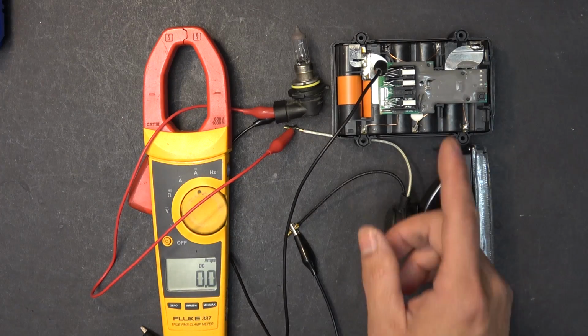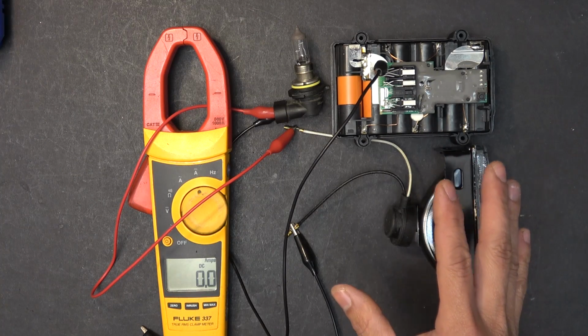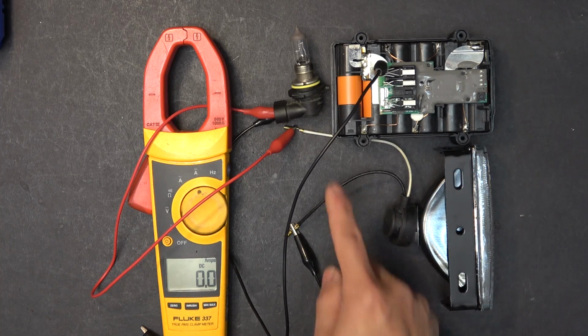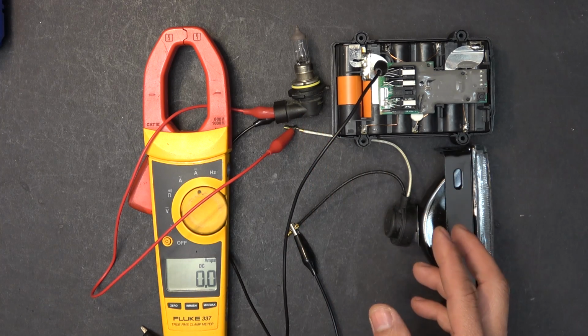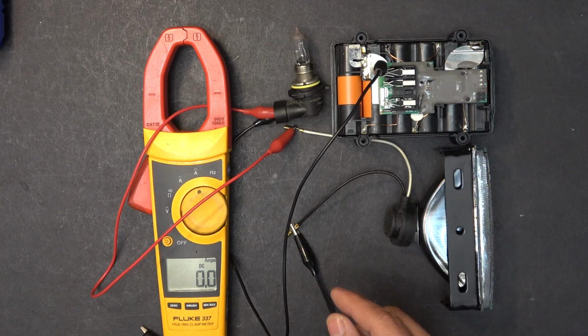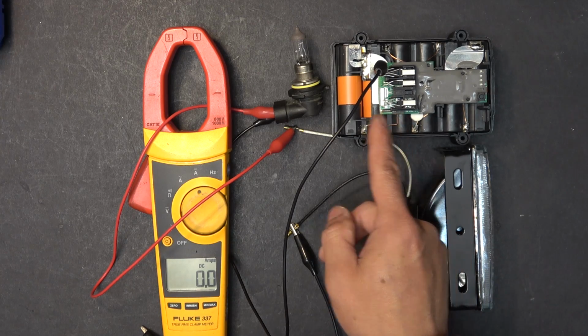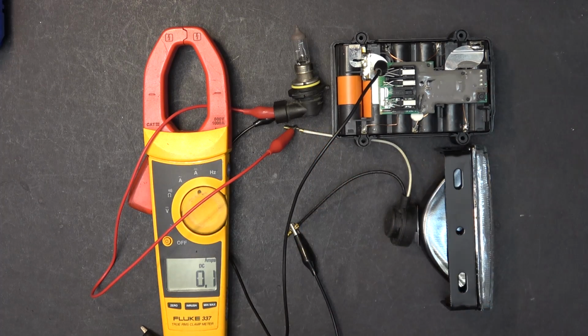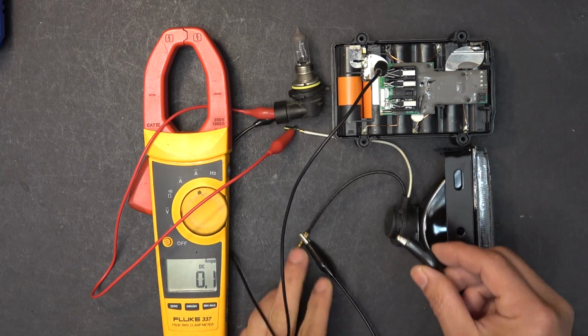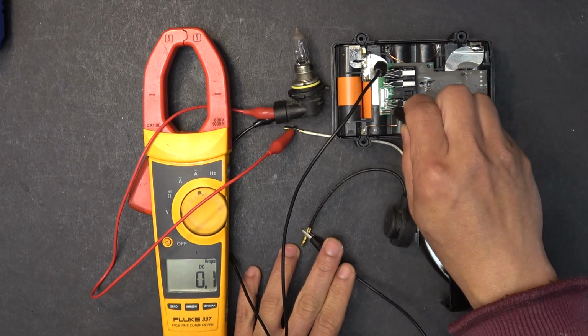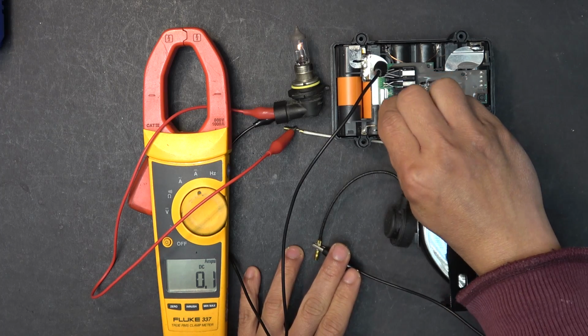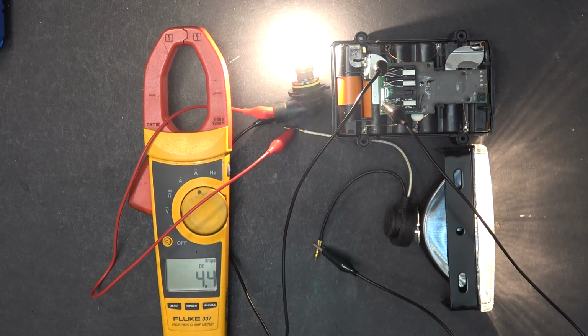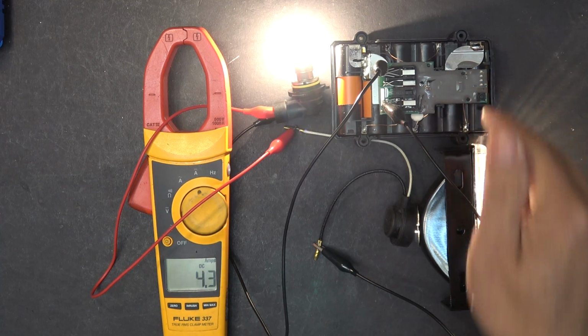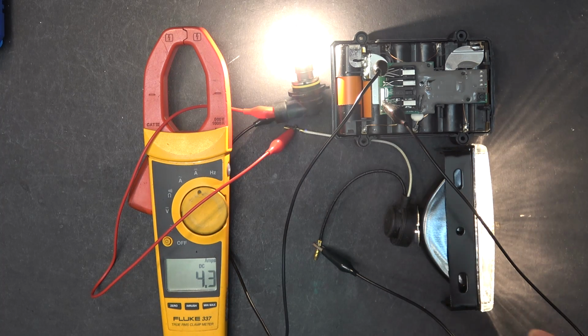Just want to be sure the BMS is working properly. I'm going to do a discharge test. I got 2 headlights here, these are 12 volt incandescent. And because the battery is 24 volt, I connect these 2 headlights in series, and just going to connect them to the battery and do a discharge test. It's running at 4 amps. So at this rate, this 4 amp hour battery will be completely drained in less than 1 hour.